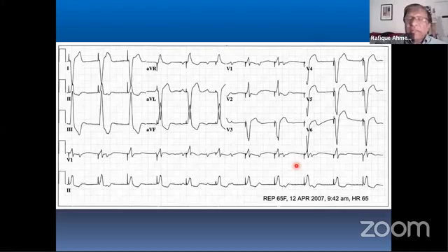So these are the mechanisms. This is a Medtronic pacemaker. If one day it shows up in your office, a dual chamber pacemaker at a rate of 65, you know that this pacemaker has become ERI. That's the default program, and it is done so that the pacemaker doesn't stop working suddenly, to save battery. In this mode, you won't be able to program too much. It will not be rate response. It will conserve battery as much as possible.